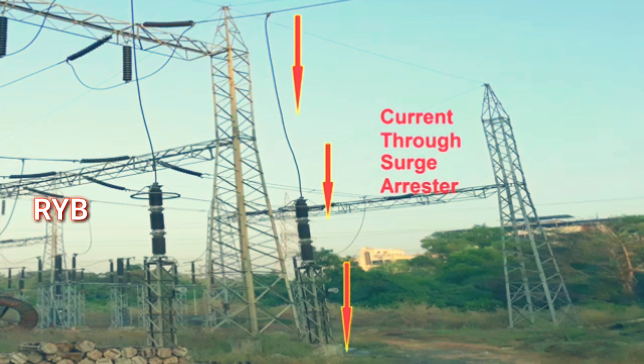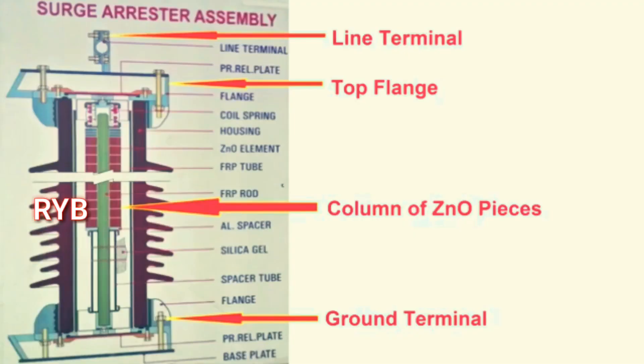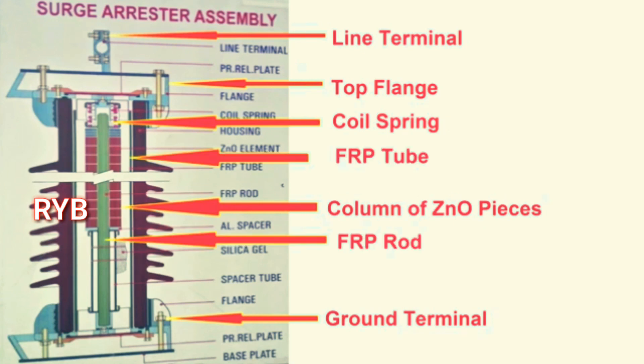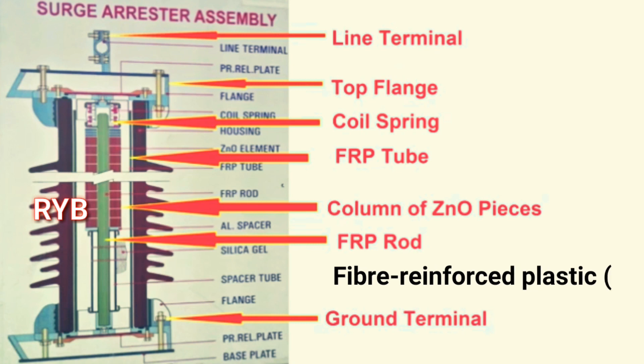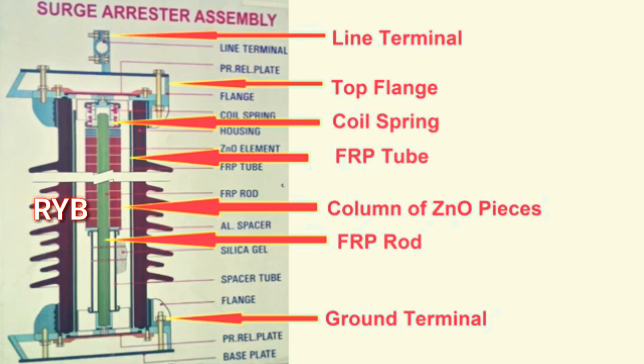In a substation, the lightning arrestor or surge arrestor is connected with one terminal to the line and another terminal to ground. Whenever lightning occurs and high voltage reaches the transformer, the lightning arrestor diverts it. The construction includes a line terminal, top flange, coil spring, column of zinc oxide pieces, ground terminal, and FRP rod — these are the different parts of a metal oxide semiconducting material type lightning arrestor.